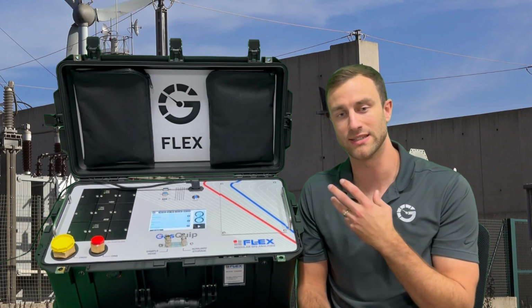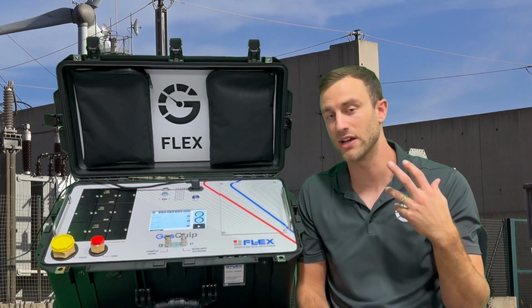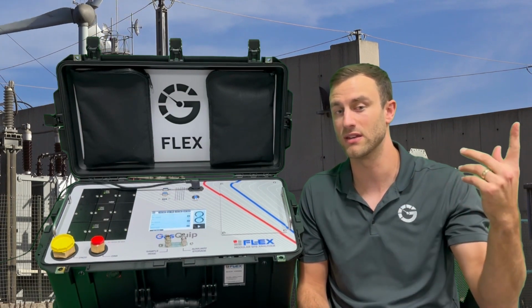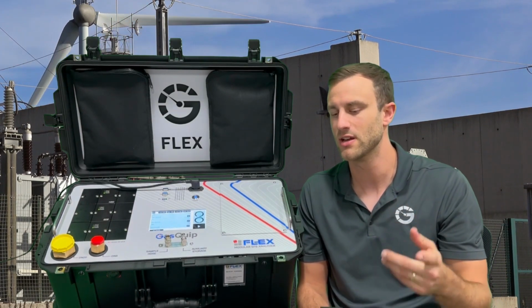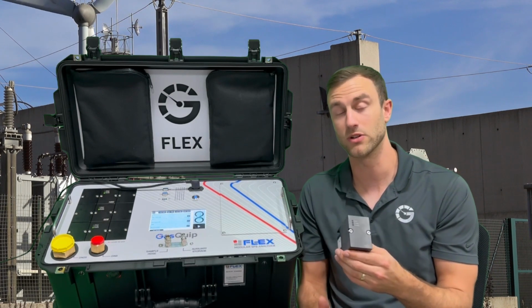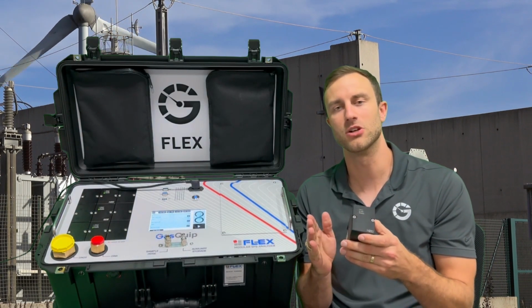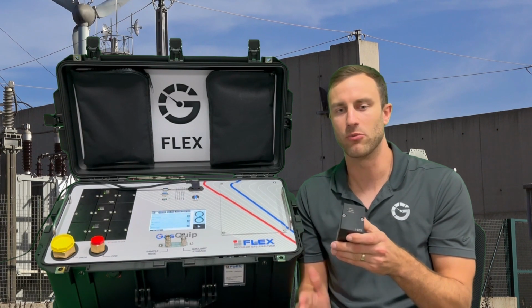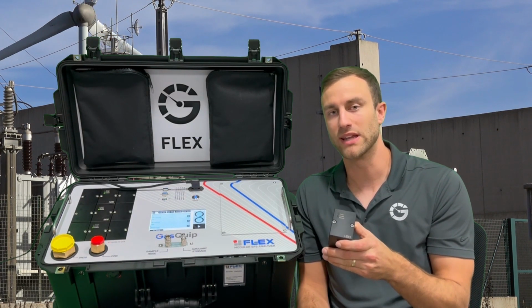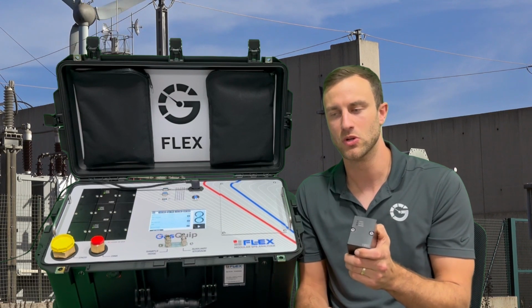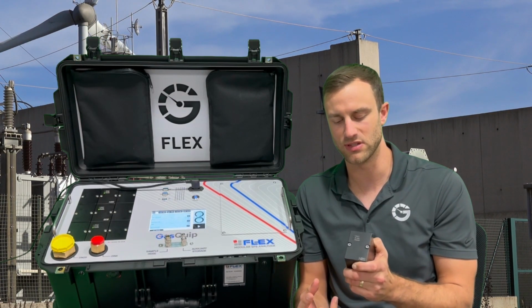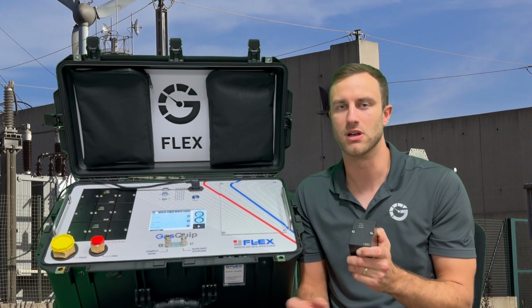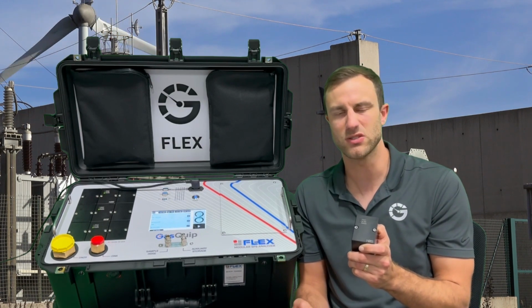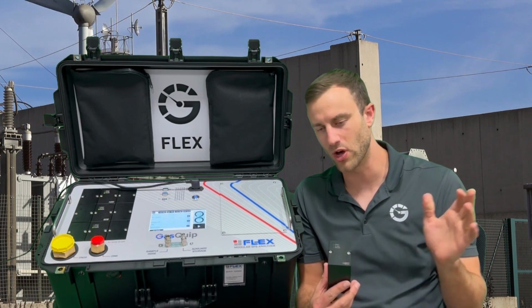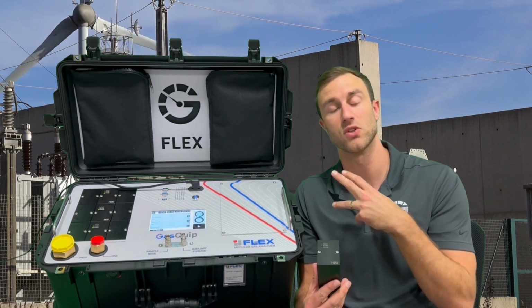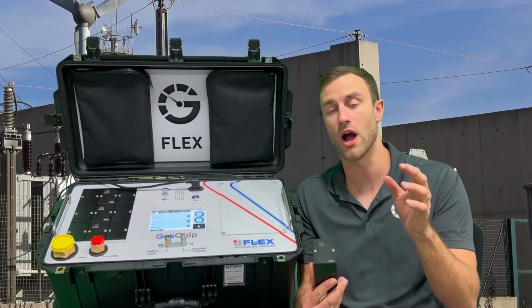Most customers realize that with a lot of these other devices, they'd have to test 1, 2, maybe 3 times before that system would start to read drier tests. So what we did is we built a heater into the tip of the sensor, and we run that heater prior to running a test, and that helps to dry out that sensor, because a lot of times the moisture will build up on the tip of the sensor and it's kind of sticky, so it's hard to get out. So usually you have to run 2 or 3 tests' worth of gas flow across that sensor to get it to dry out.